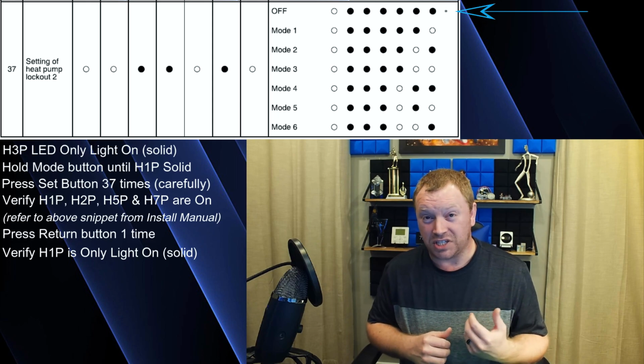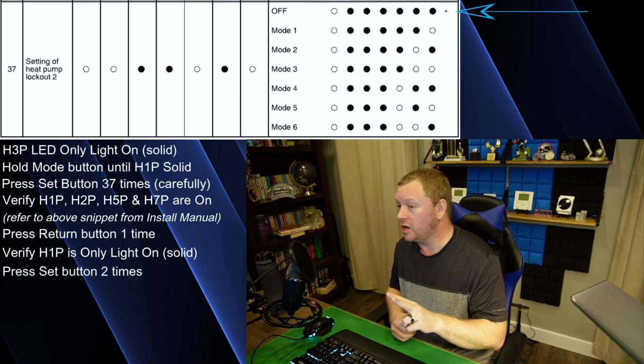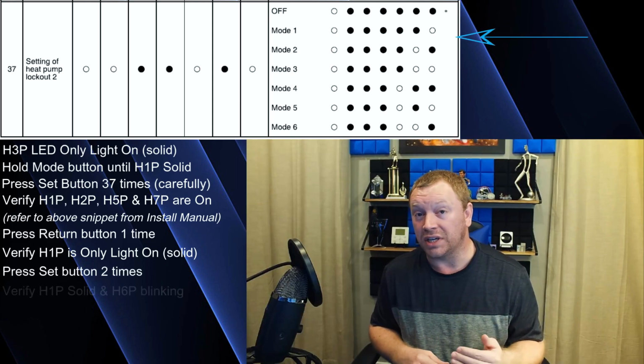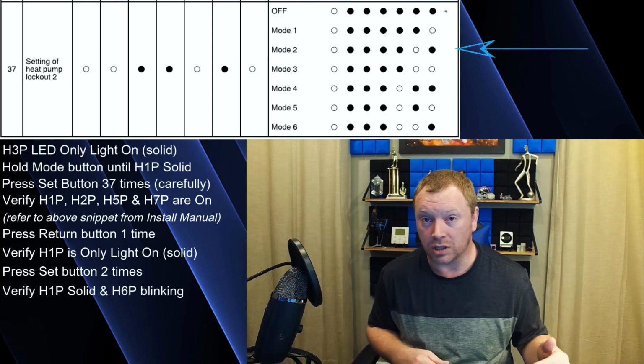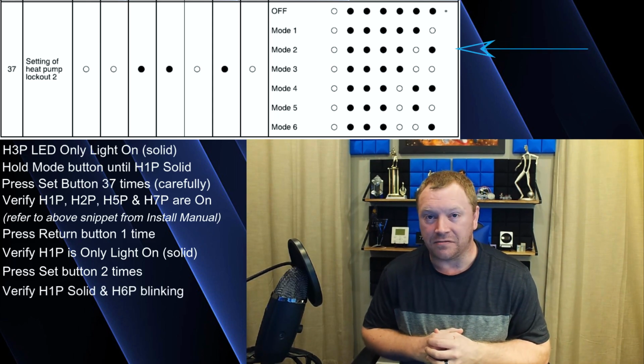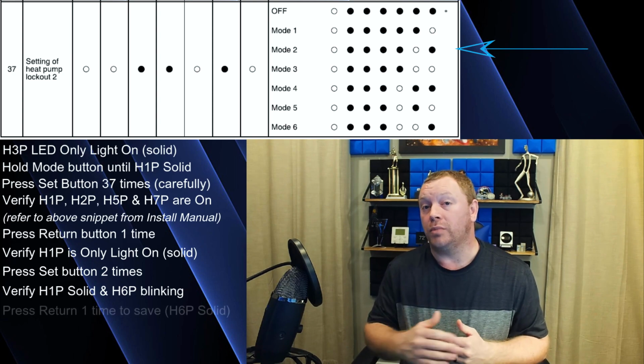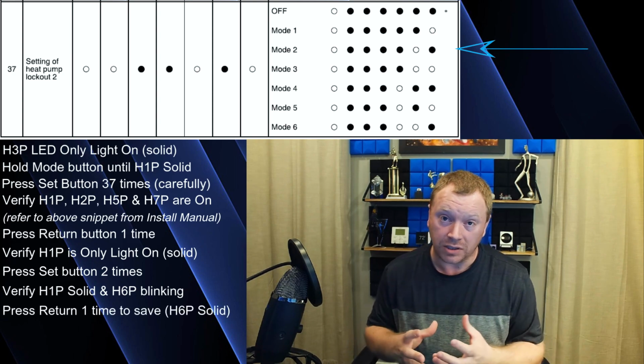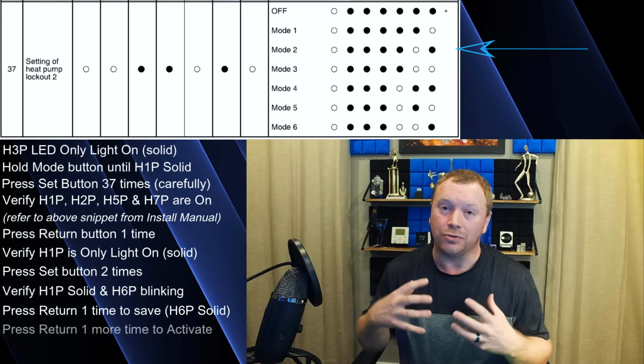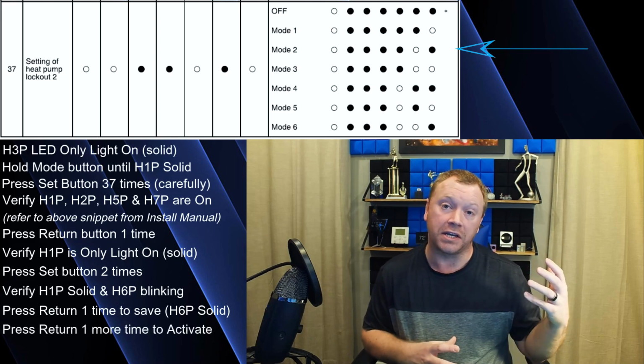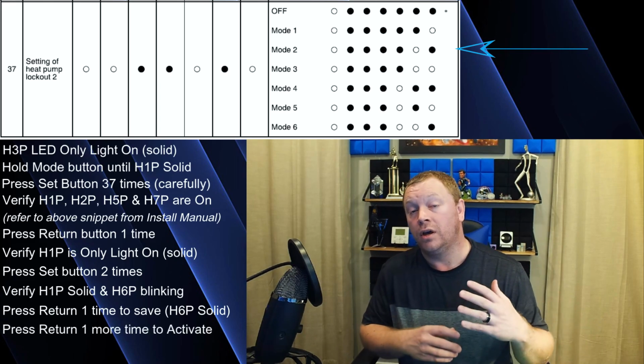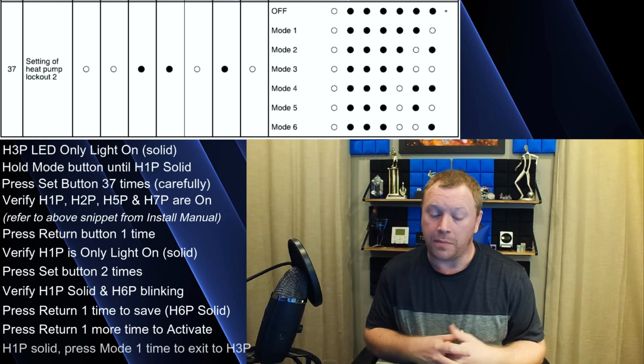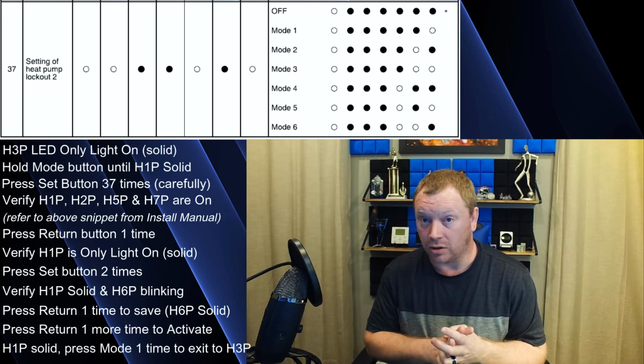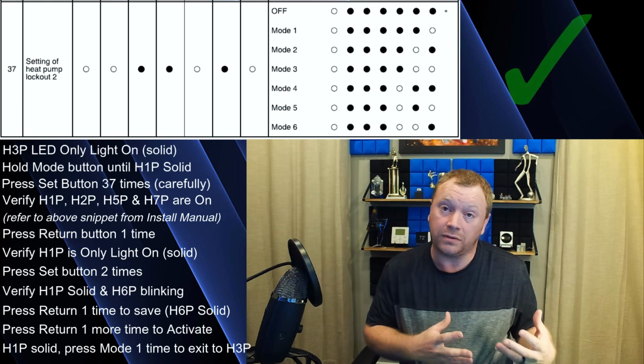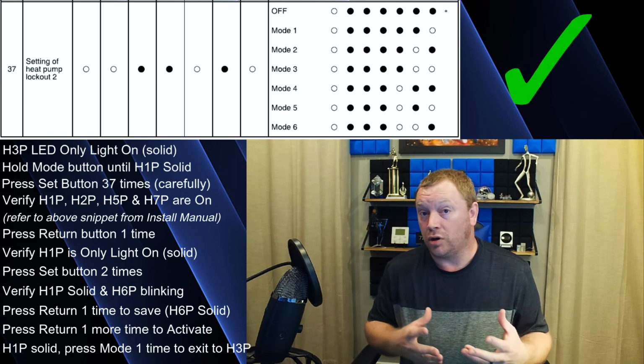So what you're gonna do is simply press the set button 2 times. H6P should be blinking, H1P will still be solid, and now we need to save that setting. So you hit the return button and it goes from a blinking 6 to a solid 6, and then you press return again to activate that setting. It goes back to H1P, no other lights are on. You're good to go. You can hit the mode button to escape. It goes back to H3P solid all by itself, and now you have successfully turned on the heat pump lockout field setting.